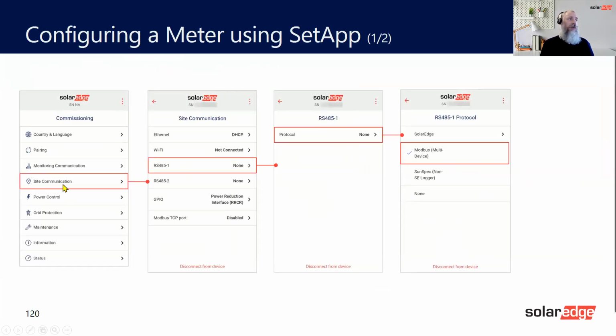You've got site communication, not monitoring, site communication, RS485, RS485. You then set up the protocol. Remember, this is a meter, so we want to go to Modbus multi-devices. Why multi-devices? Because it allows you to put the battery on there.